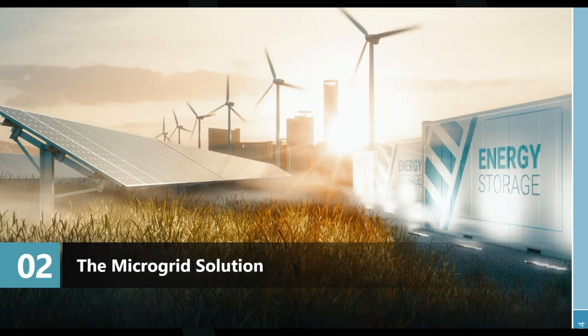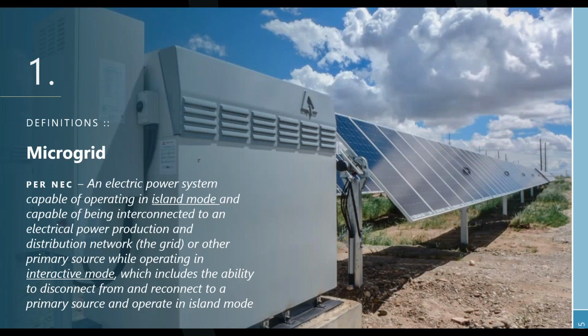So, the microgrid solution. To start off, I wanted to bring the latest definition, which has been changing, as defined now in the 2023 electrical code: an electrical power system capable of operating in island mode, disconnected from the grid, and capable of being interconnected to an electrical power production and distribution network, that's what they're calling the grid, or other primary source, while operating in interactive mode. That interactive mode is often called grid interactive mode or blue sky mode, which includes the ability to disconnect from and reconnect to a primary source and operate in island mode.